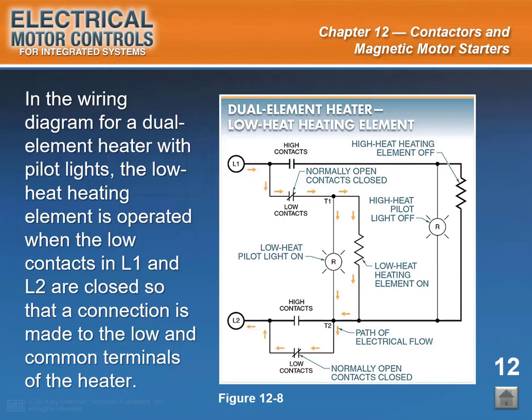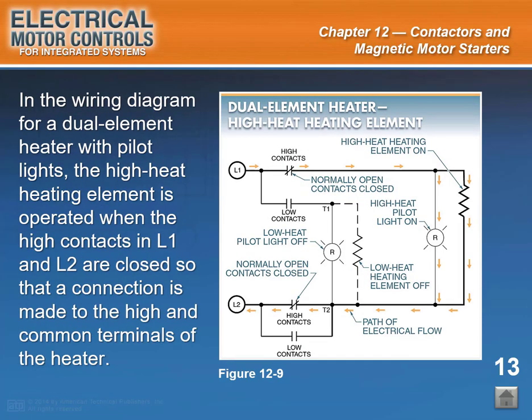Wiring diagrams may be complex. For example, this wiring diagram for a dual-element heater with pilot lights contains various circuit paths. In this circuit, the low-heat heating element is operated when the low contacts in L1 and L2 are closed so that a connection is made to the low and common terminals of the heater. This allows the low-heat heating element to be energized. End of slide 12. Start of slide 13.